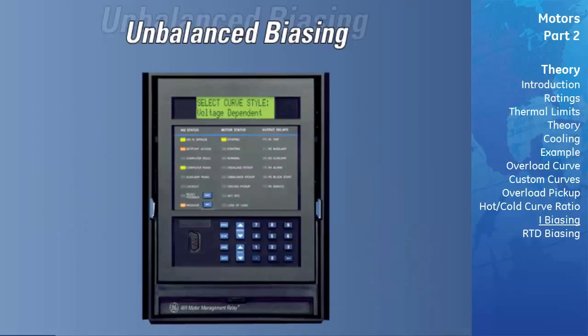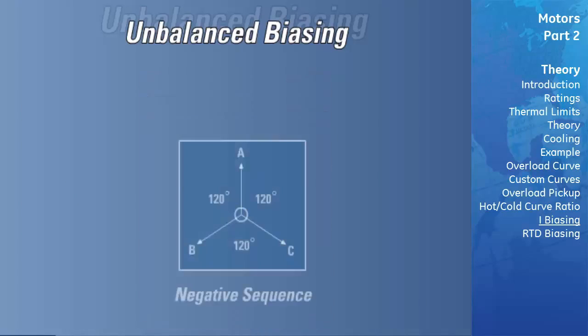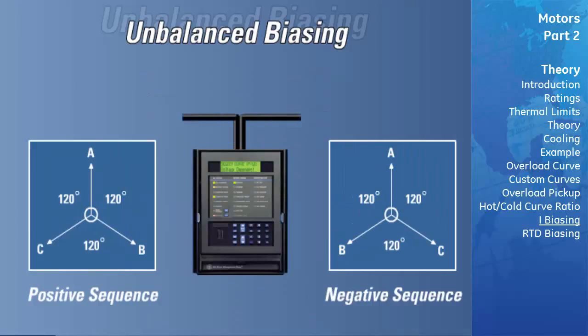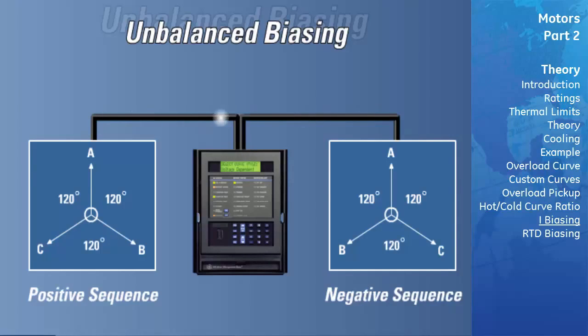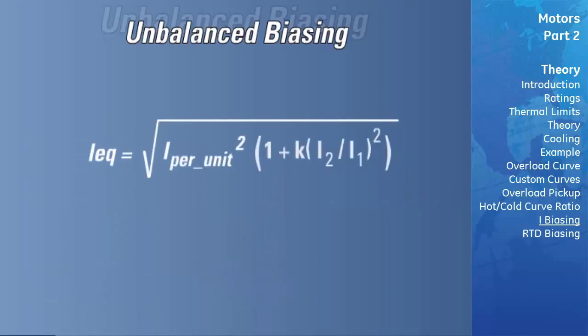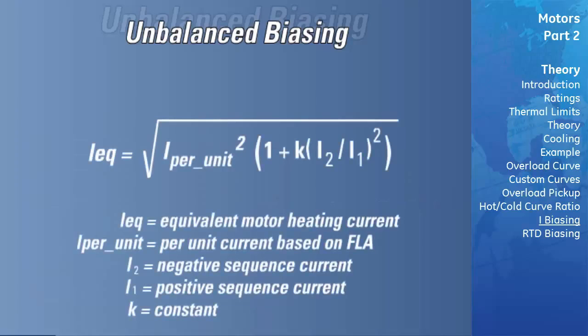The GE Multilin relay measures the ratio of negative to positive sequence current. The thermal model is biased to reflect the additional heating caused by negative sequence current when the motor is running. This biasing is done by creating an equivalent motor heating current rather than simply using average current, I per unit. This equivalent current is calculated using the equation shown.